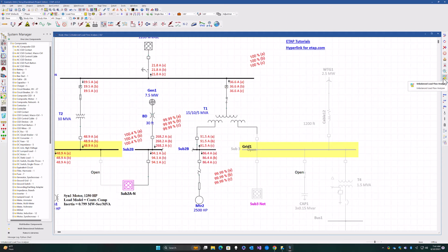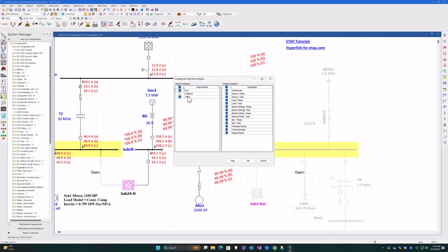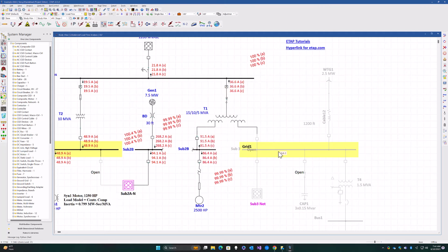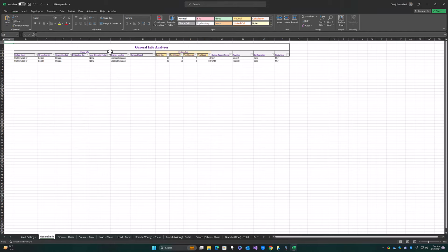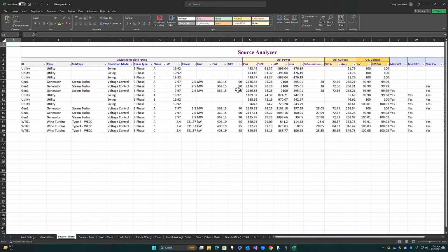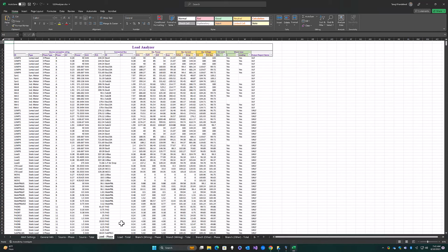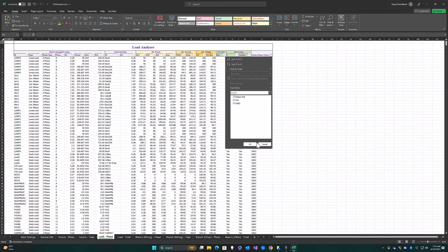And now we can go ahead and bring up our unbalanced load flow result analyzer, compare ULF and UNLF results in terms of all of these different capabilities. And what the program quickly does is puts together the general information of what you're trying to analyze. It's comparing the sources, including the operating power across each scenario. And you can also compare the total source loading, the total load connected on various buses, and of course you can also filter different output reports from here, so you can easily analyze one or the other itself.